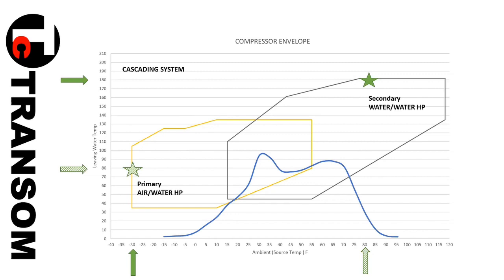On the opposite end of the spectrum, I think of my experience visiting friends in Manhattan in the winter and being roasted out of their apartments, 180 degree discharge, 180 degree radiators. So my thought was, on the more moderate temperature side, what kind of opportunities does the classic outdoor reset, temperature reset, offer you? Another way of saying it: you don't need 180 degree discharge temperature when it's above 45 degrees.